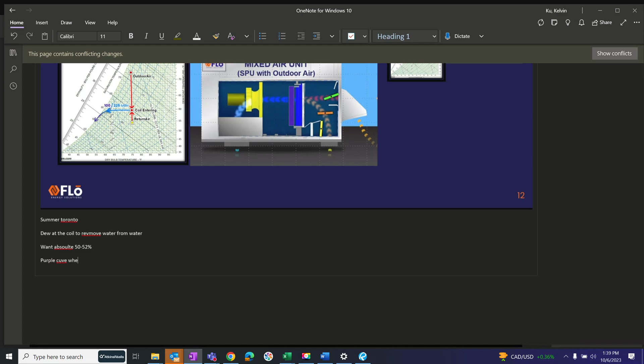This air here, in this case, if you push or you have enough capacity, even with these mixed air units, if you push them hard enough, you can get them to the saturation line and then you can start getting moisture to come out of the air. That's what we see in this purple curve here, right? That's starting to dehumidify. And then, as you mentioned, you can't drop air back into a space at 55 degrees, or even lower at times, because if the ambient air has a higher moisture level, what's going to happen? All your ducts are going to sweat. You're going to have dripping off of your ceiling, and obviously you're going to get other problems with your cases.